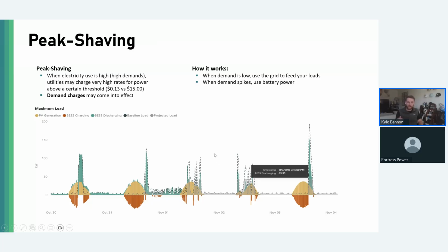Peak shaving is very dependent on your load profile and whether you're hit with demand charges — a threshold where above a certain kW, you're charged, say, $15 per kW. This NREL map, a bit out of date from 2023 or 2024, shows the breadth of demand charges across the country. California has some of the highest, which is partly why the battery and solar market does so well there, offering the best return on investment, though there are pockets of high demand charges all across the country.